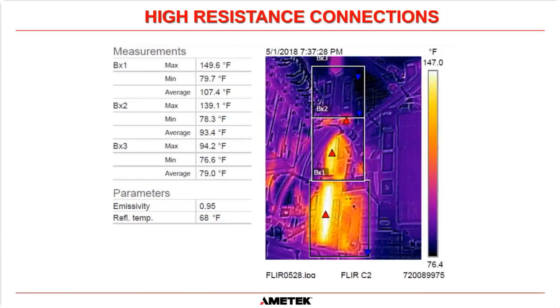And at the opposite end of that spectrum, this picture was taken on a startup for one of our UPSs. You can see this is a choke or an inductor, and there's three because this is a three-phase system. I think this is on the output choke of this UPS. So there's three for each phase. It's 1, 2, and this top one here, 3. You can see box 1 has a maximum temperature of 150 degrees. Box 2 is about 140 degrees. That's normal. Box 3 only has 94 degrees. So that inductor is not hot when it actually should be.